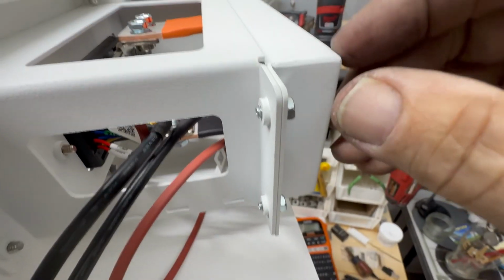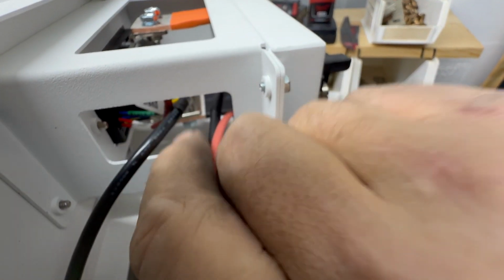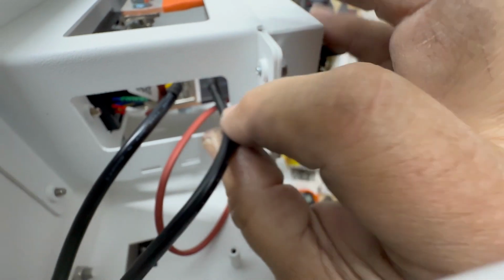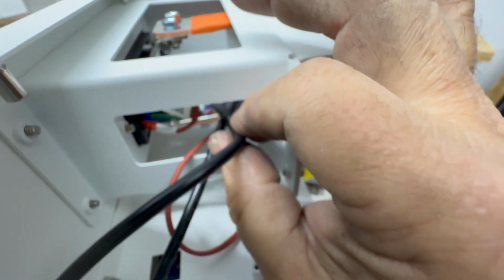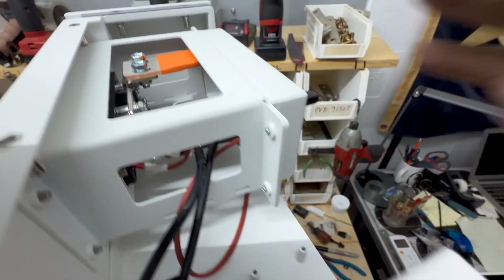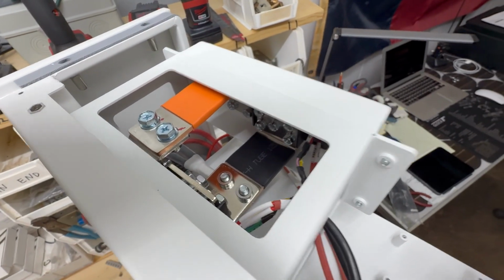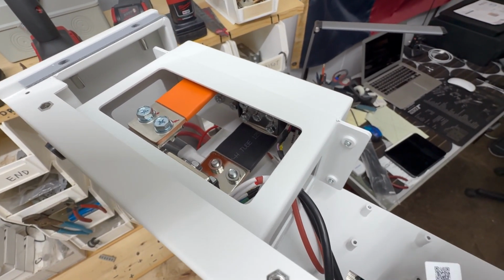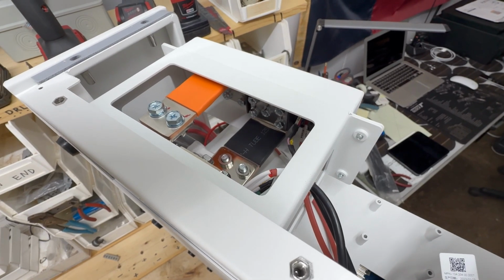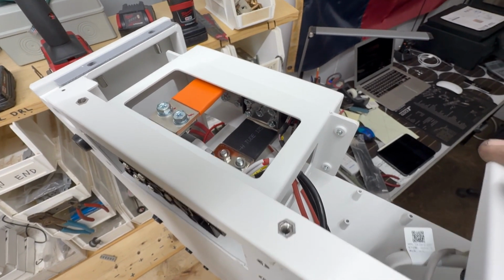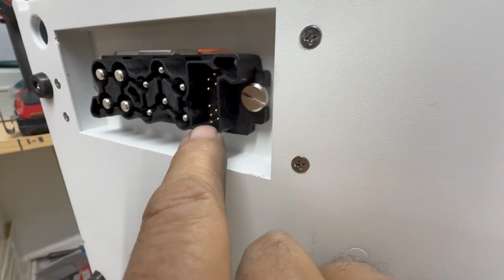I did see, got to dig in here a little bit. There is, I guess it's RS485 or CAN - the upper battery cable to the BMS is here, and the lower battery cable that gets to the BMS is here. So they have a daisy chain. You don't have to plug Ethernet cables - well, they're not really Ethernet - you don't have to plug RJ45 style connector cables between batteries. That happens with the pogos here.